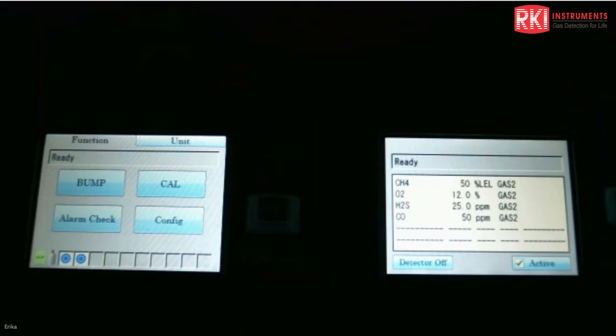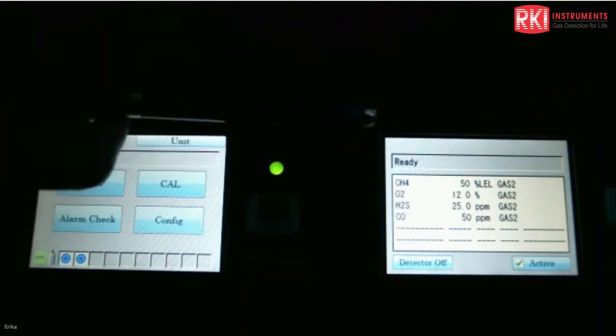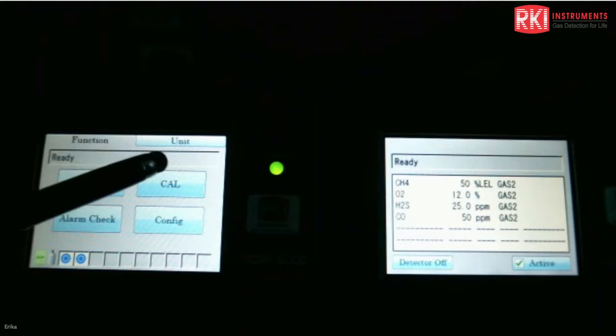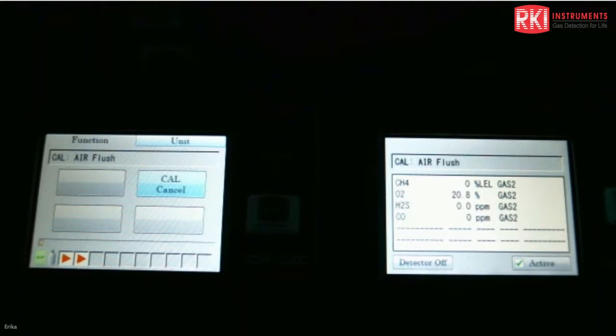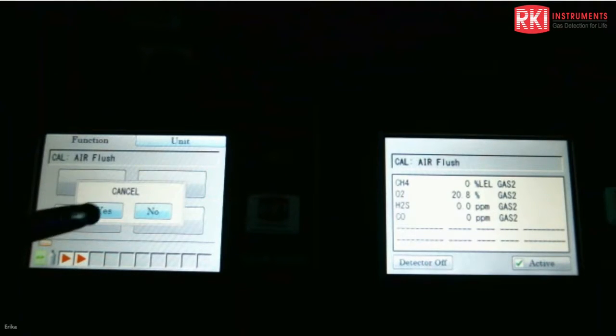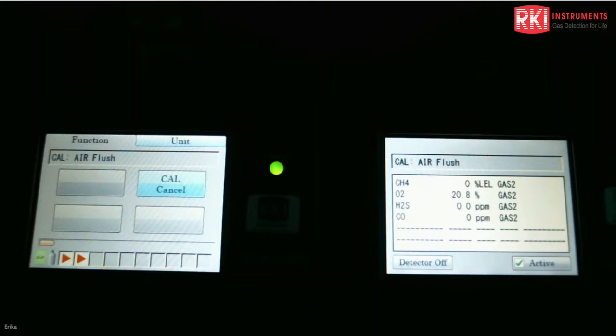Okay, so now we'll do a calibration. I have all my gases set up, so you can see this one would have the HCN, and it's going to run the HCN gas first. This one just has a standard 4 gas, so it's just going to run gas 2, and it's going to skip gas 3 and 1. So I'm going to start the calibration now. Right now it's going through the air flush, and you can see the status there. You can hit the cal cancel button if you want to cancel the calibration. You just hit yes if you want to.